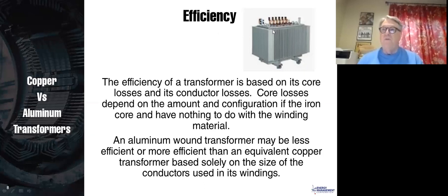An aluminum wound transformer, if you use the same conductor size, would be less efficient than a copper one. But as I mentioned, if you just make the aluminum conductors a little bit larger, then it would have the same efficiency as a copper wound transformer. So when someone's looking for the best efficiency in a transformer, typically they'll say, well, we're going to evaluate transformers based on this many dollars per kilowatt of no load losses, and that tells you the efficiency of the core, and this many dollars per kilowatt of full load losses, and that gives you the efficiency of the windings as well as the core.